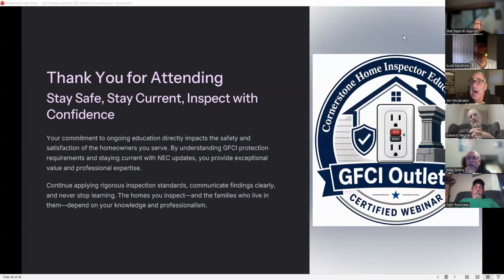Okay. So it's not grounded. However, the GFCI protection from water, that interrupted supply of electricity by moisture, is still there. And that's going to trip the outlet. It's not going to help, like we talked about, it's not complete protection because the ground protection does other things for defective appliances and stuff like that. But if you press that button physically, it will trip. And then you just reset it. But it does protect you from electrocution from water intrusion or moisture, even though the outlet is non-grounded.